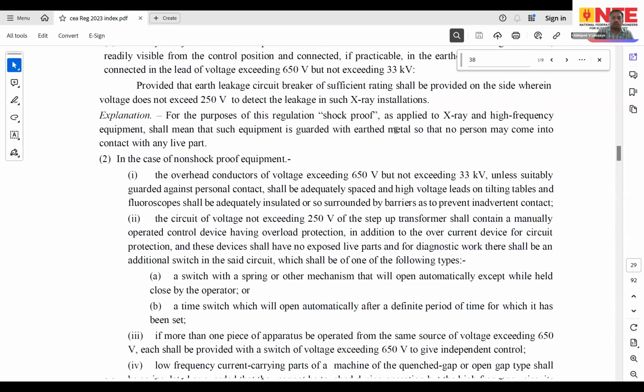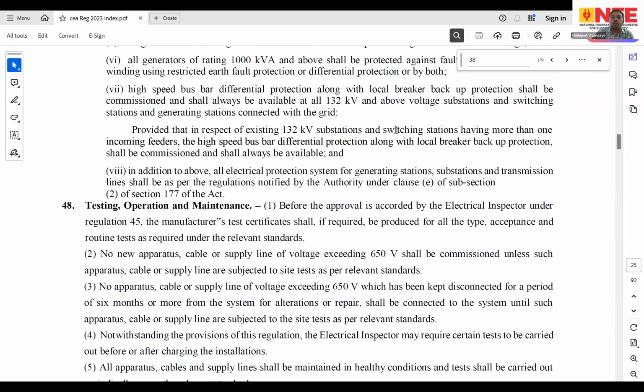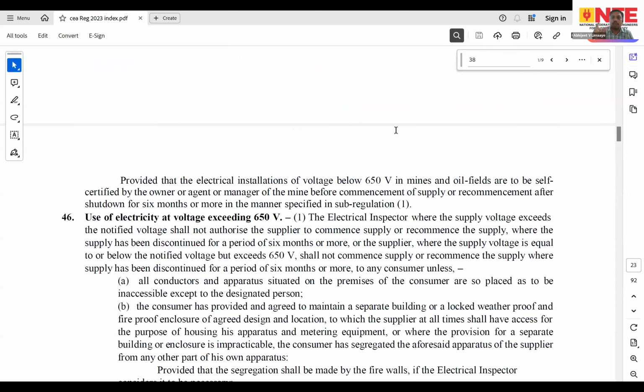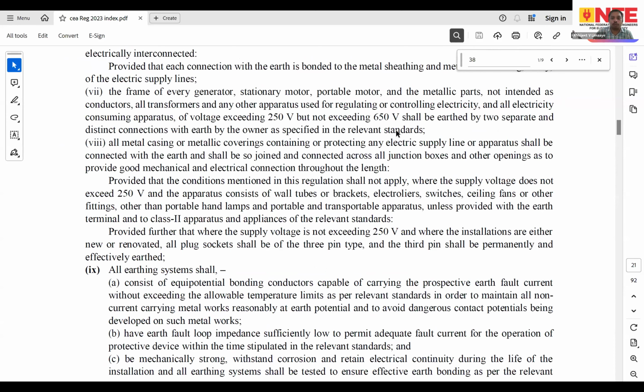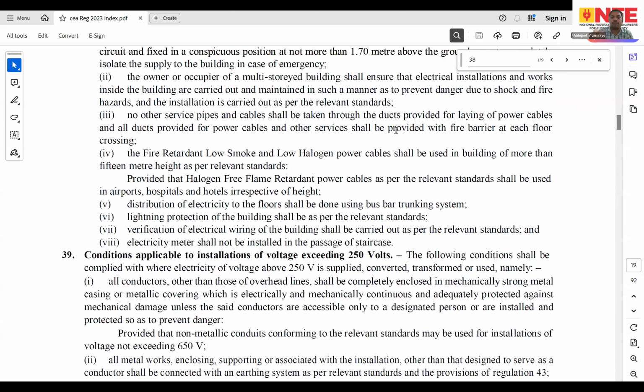I think in IS 732, it specifies that cables should not be subjected to carrying too much current. There were earlier practices where we were using multiple runs of cable, 3 runs, 4 runs, 5 runs. So IS 732 talks about an aspect where, if practically possible, beyond 4 runs of cable need not be used. They can be substituted by bus trunking. So that is the practice specified by the standards.